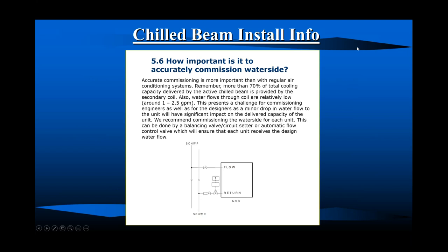Okay, let's start off with part of an installation manual from a chilled beam manufacturer. Accurate commissioning is more important. That is correct. This is where we are. Accurate commissioning is more important than ever. So this is a strange system we'll get into a little bit more, the chilled beam system. Real low flows, around 1 GPM, perhaps up to 2.5 GPM. Very low flow.